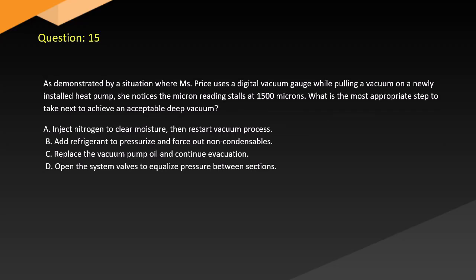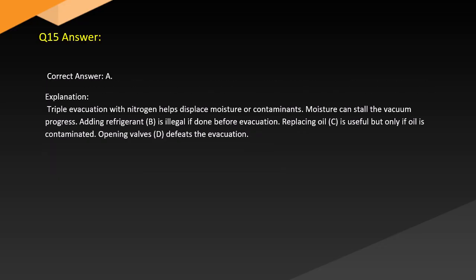Question 15. As demonstrated by a situation where a technician uses a digital vacuum gauge while pulling a vacuum on a newly installed heat pump, she notices the micron reading stalls at 1500 microns. What is the most appropriate step to take next to achieve an acceptable deep vacuum? A. Inject nitrogen to clear moisture, then restart the vacuum process. B. Add refrigerant to pressurize and force out non-condensables. C. Replace the vacuum pump oil and continue evacuation. D. Open the system valves to equalize pressure between sections.